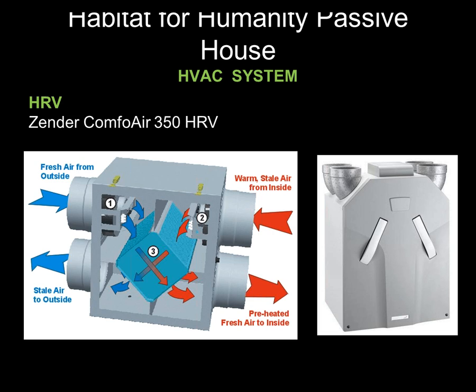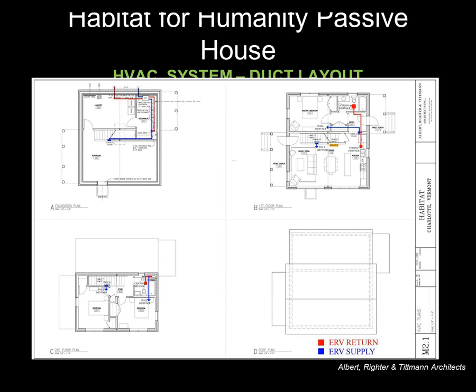Here we are looking inside a heat recovery ventilator. The transition of the heat energy from the exhaust air to the incoming fresh air that we mentioned. What's really important, as I said before, about these units is not only the efficiency of the heat recovery, but the amount of energy it takes to run this unit. And if you're working in the Passive House Planning Package, you will be asked to input that information into your energy model so you can see how that impacts the overall energy performance of the building. Here we are looking at the ventilation system of the building. Very simple: supply to all the living spaces, exhaust at the bathrooms, and exhaust in one place at the kitchen.